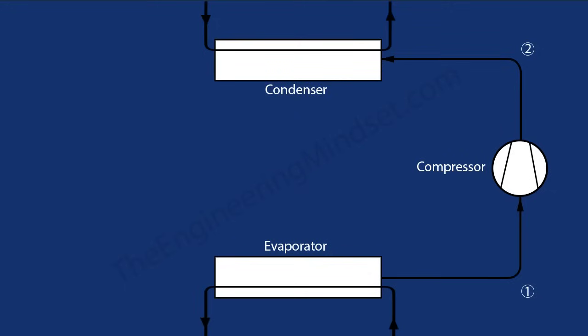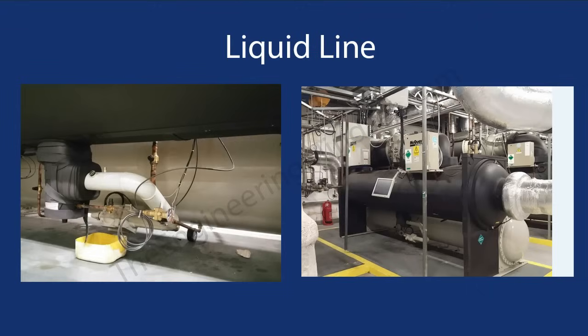As the refrigerant leaves the condenser it travels along what's known as the liquid line, which we'll refer to as Point 3 on the graphs. This is the liquid line you can see here — exiting the condenser, passing through and going into the expansion valve. There's also a king valve — this large block here — which isolates and traps the refrigerant inside the condenser should you ever need to perform maintenance.